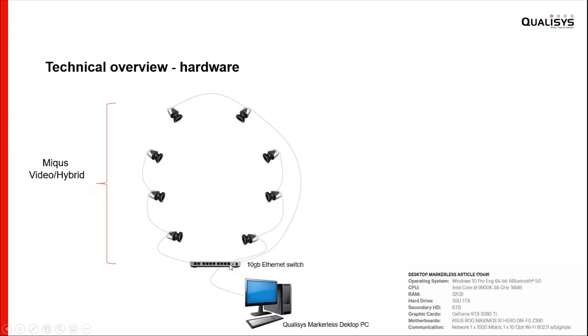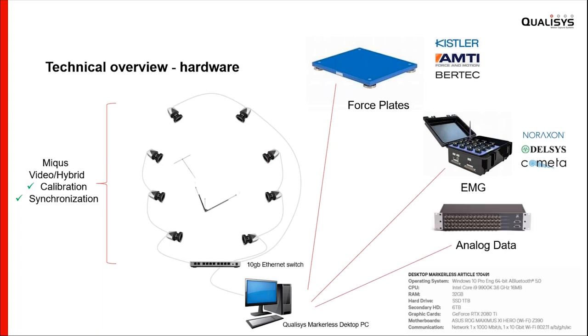The hardware setup looks very similar to a standard mocap system, except all cameras must be video or hybrid cameras. Because of the amount of video data, there is some special hardware required: a 10 gigabit Ethernet switch and a powerful computer to keep markerless processing time reasonable. With that setup, you calibrate the same way as a marker-based system and time synchronization is identical. This means you can add force plates, EMG, and analog data just like in a standard 3D mocap setup.